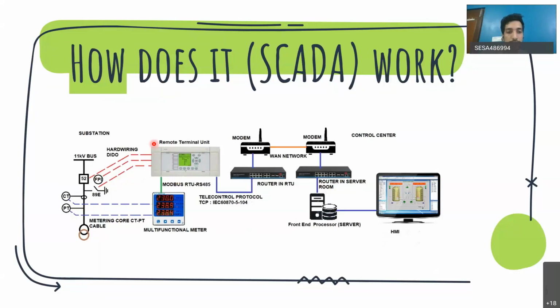So data is first read by the remote terminal unit from the actual bay. From there, through some communication equipment, it flows out from the substation first to the local area network. Then you have some communication paraphernalia, and through WAN, wide area network, for long distance communication, they communicate to the centralized communication center, where there is one more router for receiving the data.